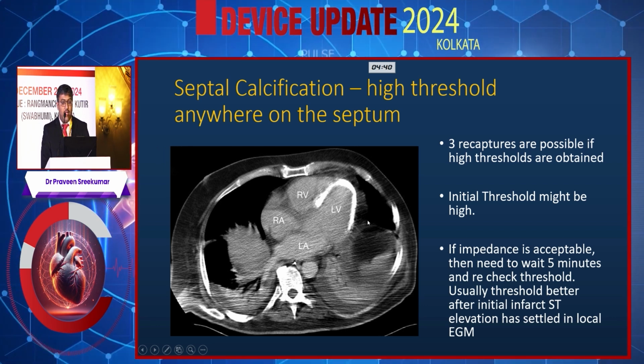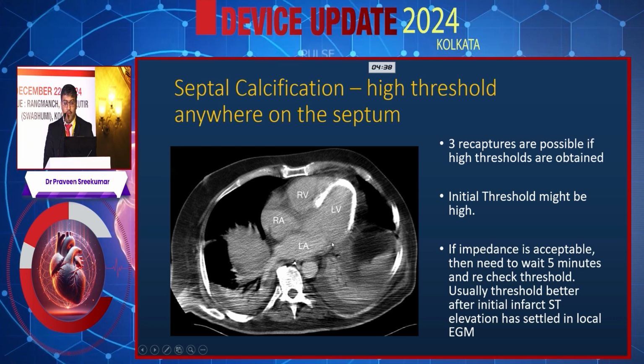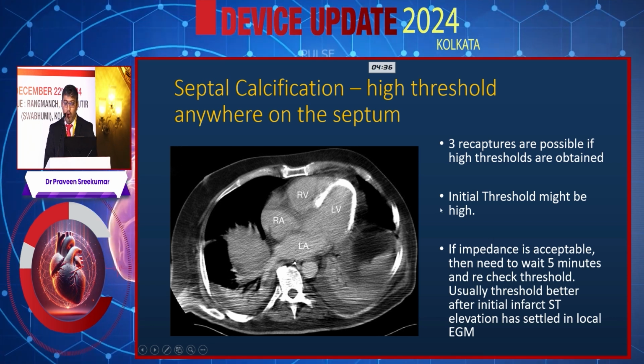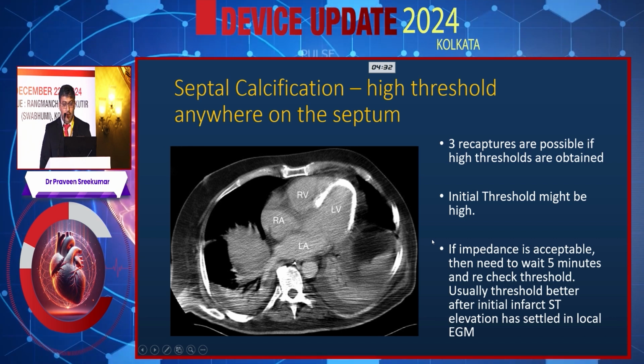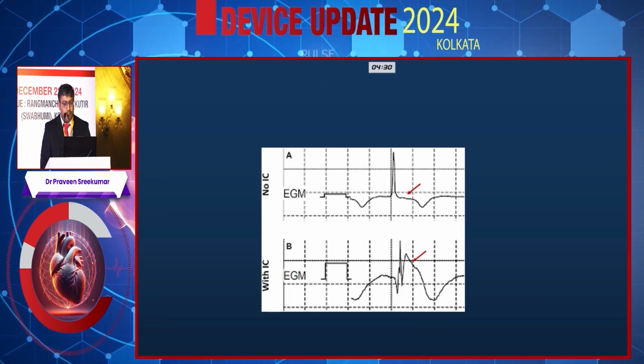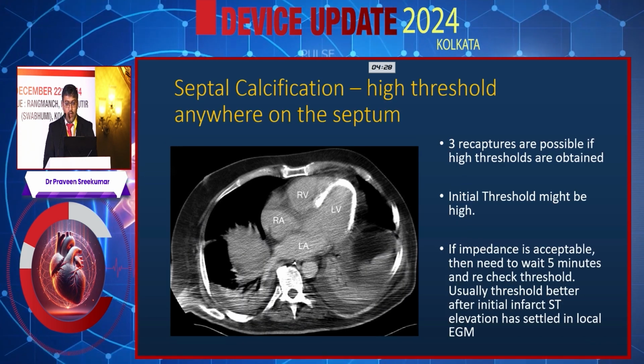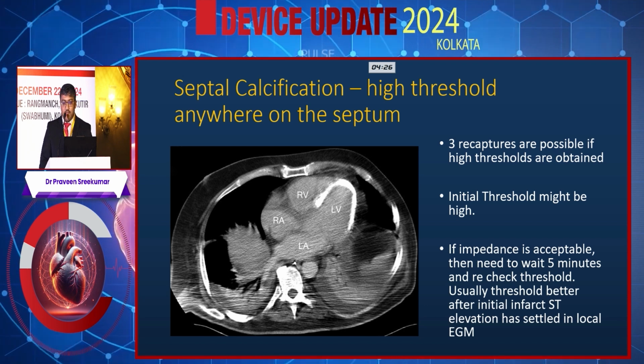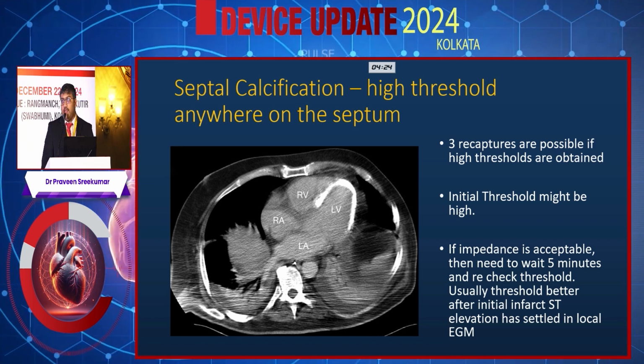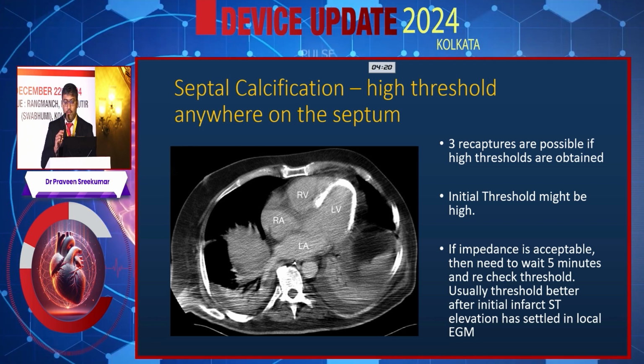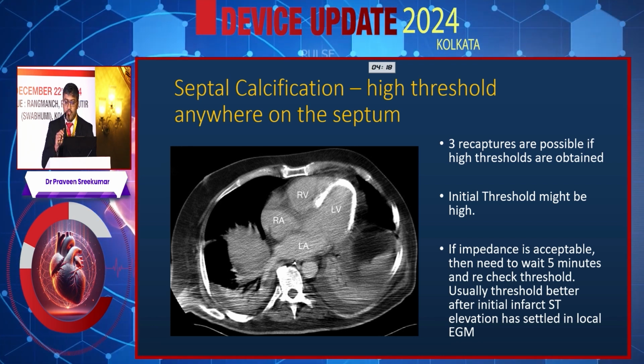So you may have a very calcified LV, and it will sometimes be very difficult to screw in or place the tines, so the threshold might be very high. This is something which is possible, especially after implant, if the impedance is acceptable. They say an impedance of less than 500 is not very good. There is a higher risk of higher thresholds post implant.